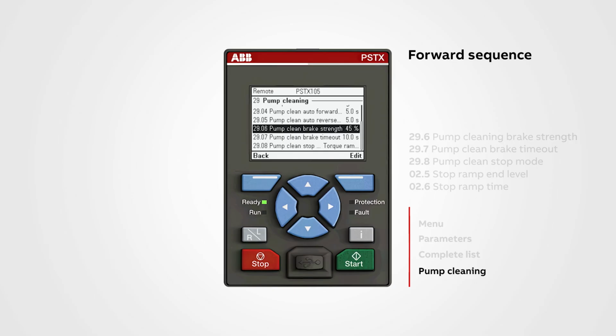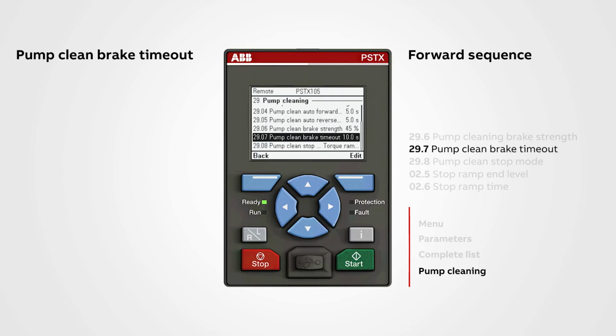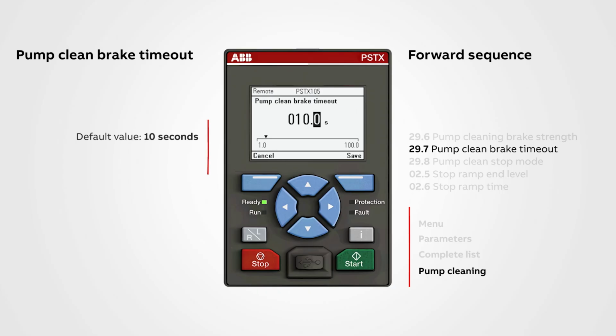Okay, now we're reaching the end of the how-to, but let us look into the last parameter, 29.7, pump clean brake timeout. This parameter will determine how long the brake is activated. The default value is 10 seconds, and it is settable between 1 to 100 seconds. You can increase this parameter if the brake time is longer than 10 seconds for your pump.